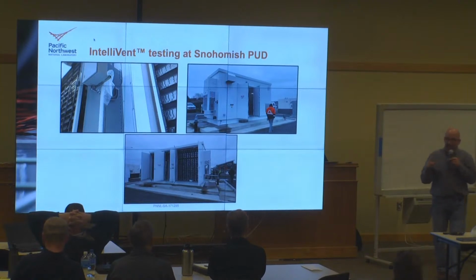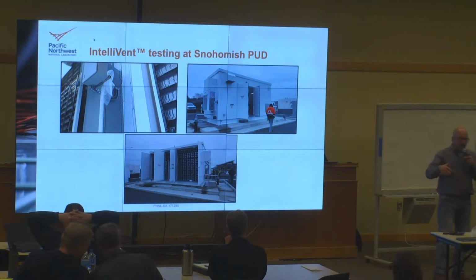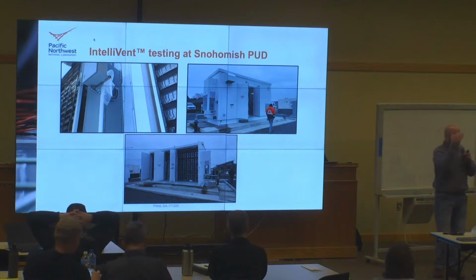There was an incident in Chandler, Arizona a few months ago, a utility-owned building with 10 megawatts, 40 megawatt hours of storage. One had a fire that set off the overhead sprinkler system. There was no exhaust system designed into it, just a manual roll-up door and a man door. Because they had no ability to get situational awareness on what was happening inside, the water stayed on. Does anyone remember how long the water stayed on, or how much water was used?